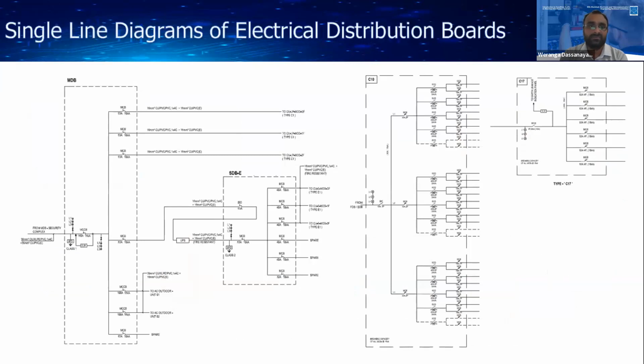This is an example of a power distribution system, which is denoted by a single line. Basically, we represent an electrical power system in a single line diagram. That means whether it is three-phase or single phase, we show only one line to denote the phase line. Here, the neutral line is not shown, because in our electrical system the neutral is considered a common conductor. Therefore, mainly we are switching or separating the phase conductors only. So the single line diagram denotes how the phases are separated into several feeders or several power distribution lines.